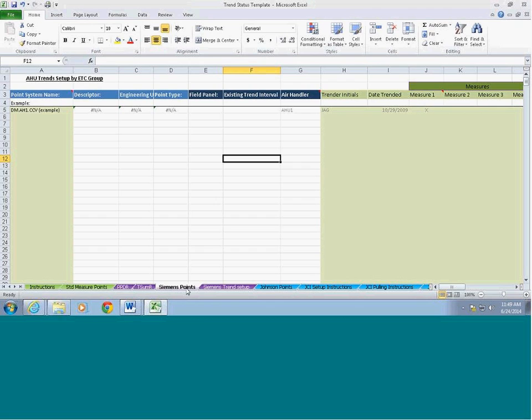And in SkySpark, there are a few pieces of information per point. One is how many records of history there are. I can't remember the tag, but I think it's hisSamples or hisCount. First of all, if that's zero or really small, you're probably not getting that data in there correctly. You might also see in SkySpark that there was a sync error that didn't correctly pull that data from TDM. So now you've narrowed down your list to a smaller portion of trends that aren't working correctly, and you can go a step back, right?